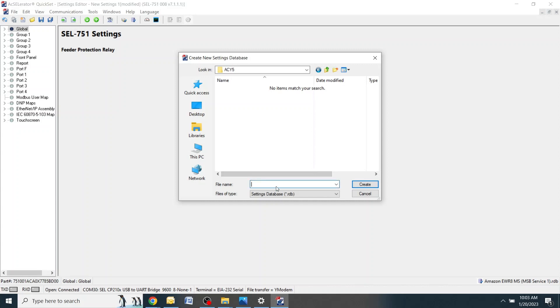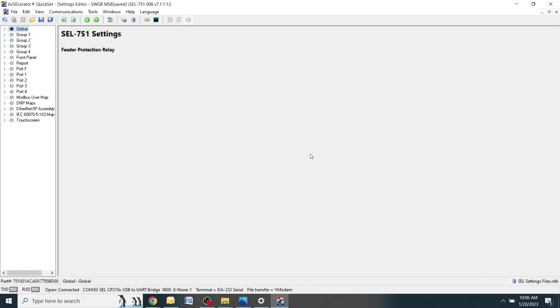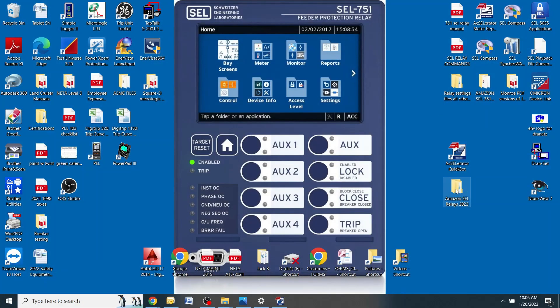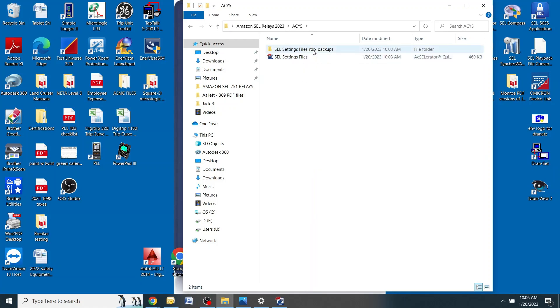Now you're going to make a new file called SEL settings files. Hit create. Down here you'll name the settings file for the particular relay that you're connected to. This one was Switchgear MSB. To verify the settings file saved, minimize the screen and go back into the Amazon SEL folder. Click on the site and verify that you have both the settings file which would be an RDB file and the backup file created. Both of these files get created automatically after you save the settings file.